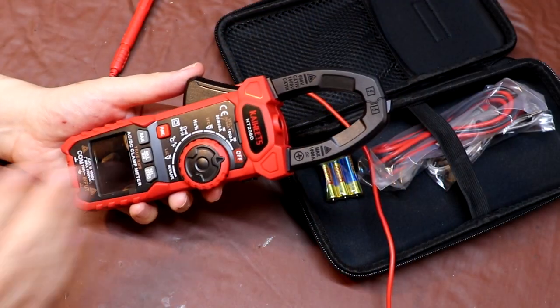So if something goes wrong when you're measuring something that can potentially deliver thousands and thousands of amps, you really don't want your meter to be connected to it, because all that potential energy is going to go into the meter and it's going to explode. So in the industrial situation, the fact that we can make a non-contact measurement, that's a huge advantage.